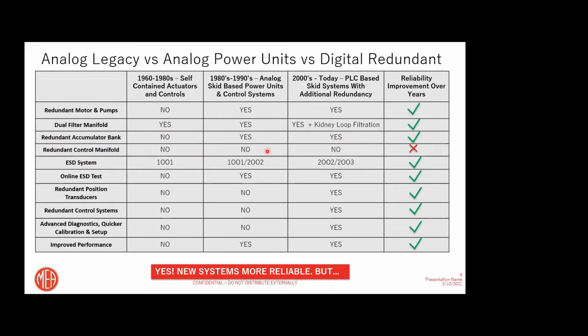Redundant control manifolds. This one we did not improve. As you remember, our servo valve and the componentry around the main manifolds are one of the most critical parts. However, we never addressed this item. Okay, let's go further. ESD system, online ESD testing: definite improvement. It went from 1 out of 1 to 2 out of 3 now, and of course we can test it online as many times as we need. Redundant position transducer, an additional improvement.